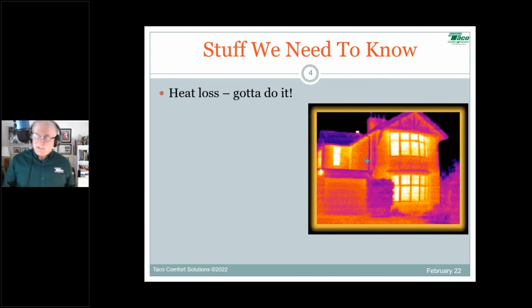First, you've got to do a heat loss calculation. That's why I included the heat loss guidebook in your handouts. It's an IBR manual heat loss, and it's very effective and simple to do. All the formulas and data you need to conduct one manually are in that handout. So you've got to know the heat loss. Figuring 25 or 35 BTUs a square foot isn't a heat loss, it's a guess. Guessing is like a hand grenade - if you're close, that's fine, but it's best to have a reasonably accurate heat loss calculation for the structure for any of this to matter.